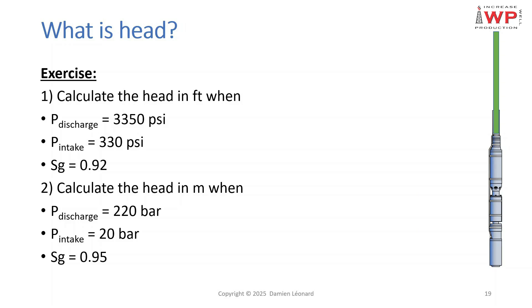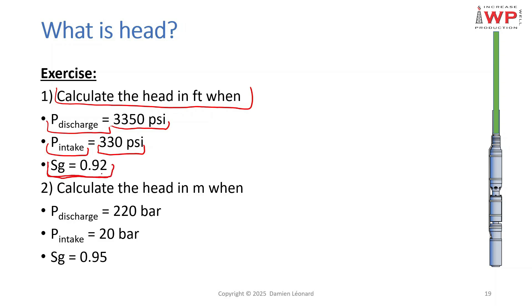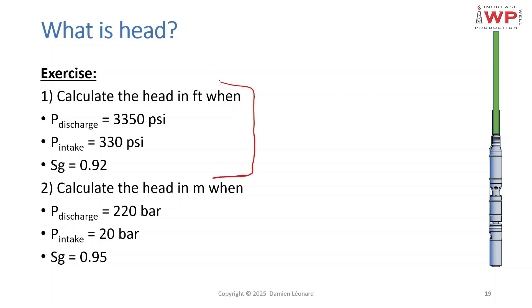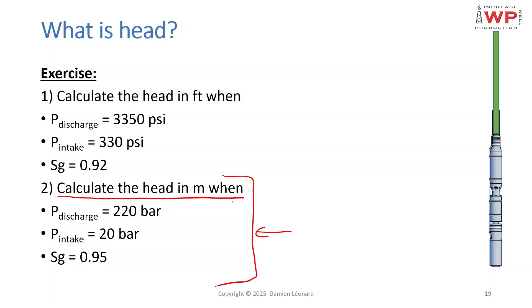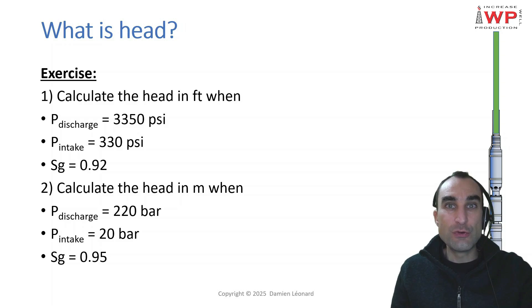Now let's practice. Calculate the head in feet using the imperial formula when the pump discharge pressure is 3350 psi, the pump intake pressure is 330 psi, and the pumped fluid specific gravity is 0.92. For the second question, use the metric formula to calculate the head in meters when discharge pressure is 220 bars, intake pressure is 20 bars, and specific gravity is 0.95. Put your answers in the quiz that follows, then watch the video with the answers.